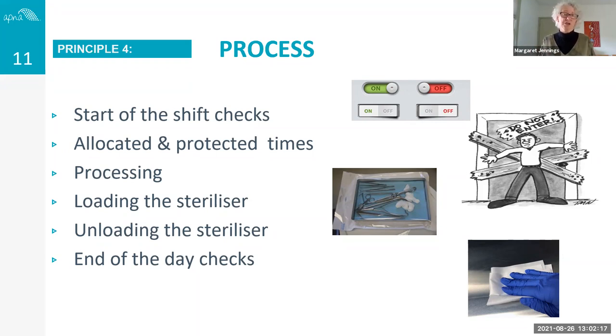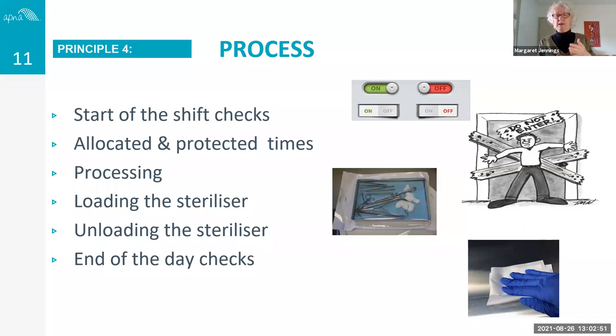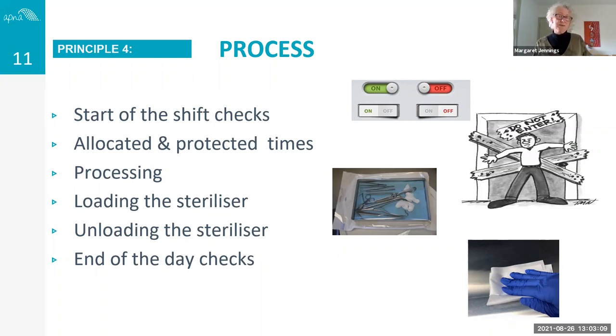Give people a sense of how long the process takes — washing 10 to 12 instruments at lunchtime might take 15 minutes. Using an ultrasonic cleaner adds about 30 minutes, but you don't need to be present for the whole 15-minute ultrasonic cycle. For packaging: you cannot pre-label or prepare a load hours in advance. Package, seal, and label just before putting it in the sterilizer — otherwise people mistake unprocessed items for completed ones. Similarly, once you set the sterilizer you can't just go home. Standards require you be there to remove the load.